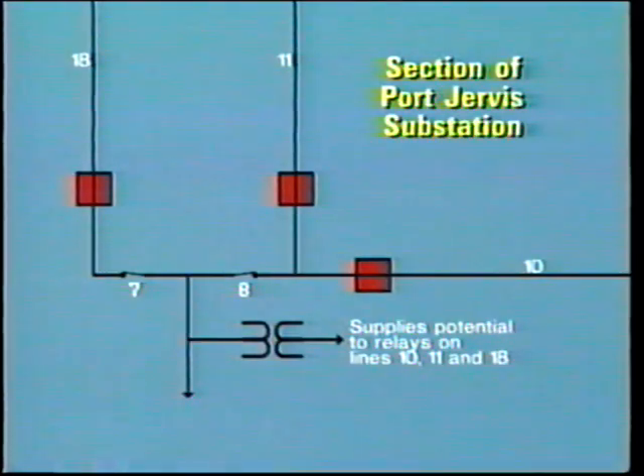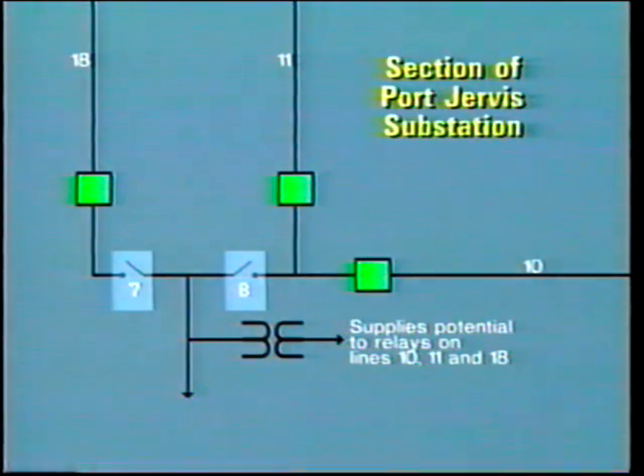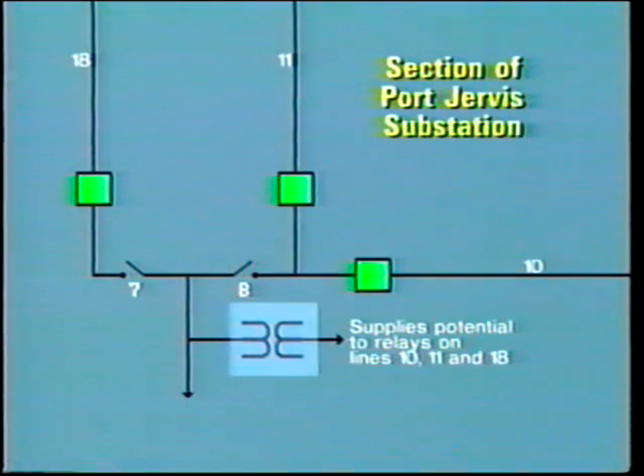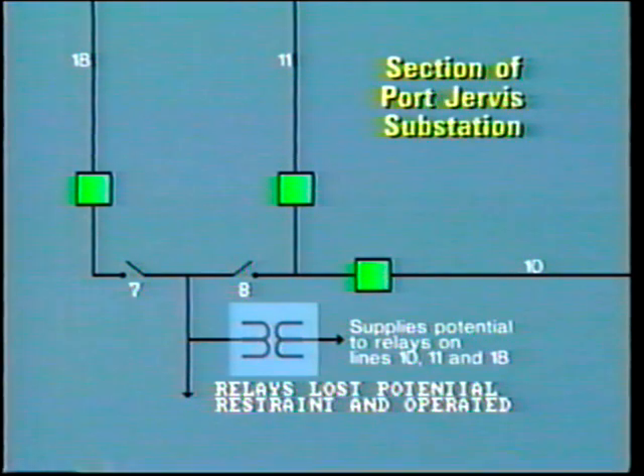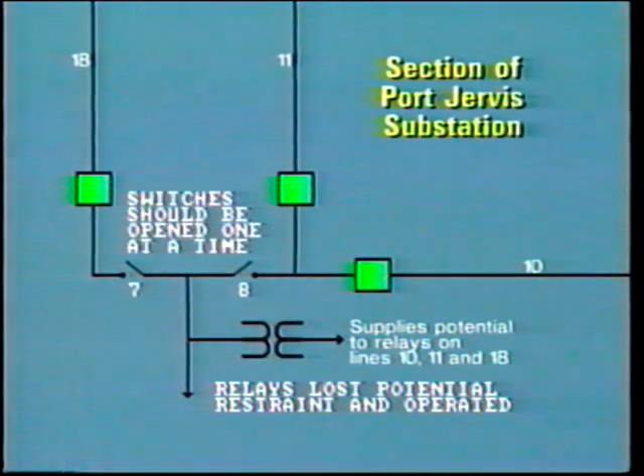A serious outage occurred at the Port Jervis substation. Line 11, Line 18, and Line 10 all tripped inadvertently due to operation of HZ and KD relays. Investigation showed that at the time of the trip, electricians had taken out a permit to work on switches 7 and 8 here. When the switches were both opened, the potential transformer became de-energized. As a consequence, the relays lost potential restraint and operated. The correct procedure would have been for the electricians to open one switch at a time. It is probable that neither the electricians nor the operators were looking for problems with VTs or CTs when they planned the operation. It is usually only relay technicians who think about these things.